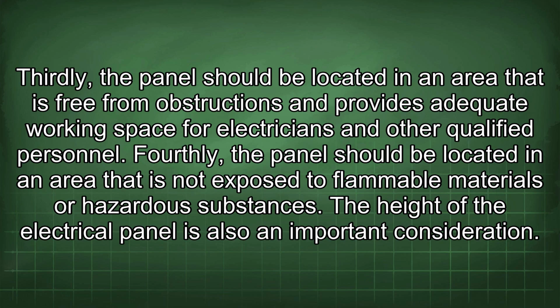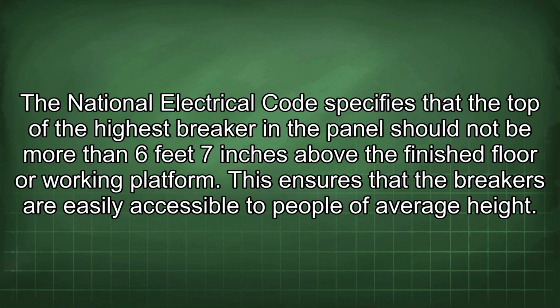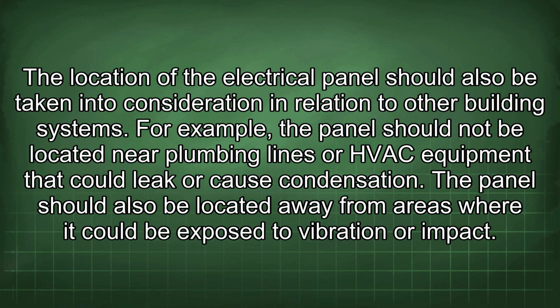The height of the electrical panel is also an important consideration. The National Electrical Code specifies that the top of the highest breaker in the panel should not be more than 6 feet 7 inches above the finished floor or working platform. This ensures that the breakers are easily accessible to people of average height. The location of the electrical panel should also be taken into consideration in relation to other building systems. For example, the panel should not be located near plumbing lines or HVAC equipment that could leak or cause condensation. The panel should also be located away from areas where it could be exposed to vibration or impact.